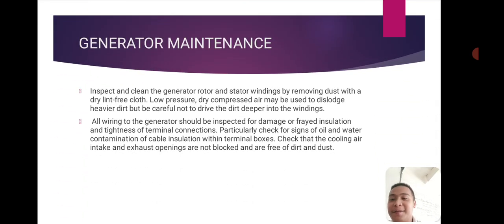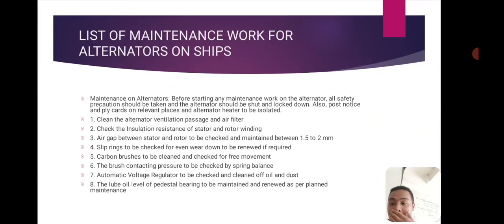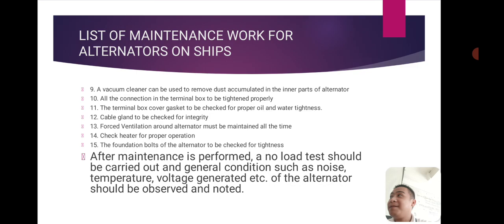Generator maintenance. Inspect and clean the generator rotor and stator windings by removing dust with a dry lint-free cloth. List of maintenance work for alternators on ship. 1. Clean the alternator, ventilation passage, and air filter. Check the insulation resistance of stator and rotor winding.